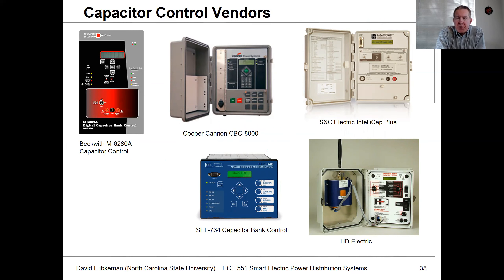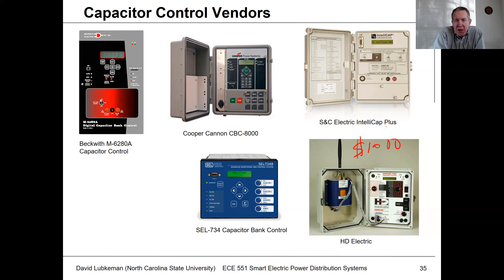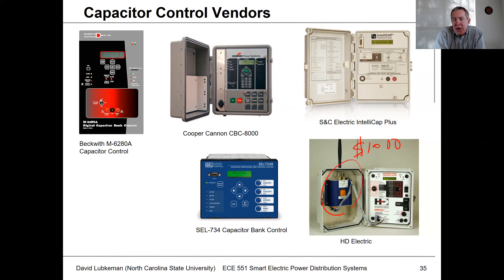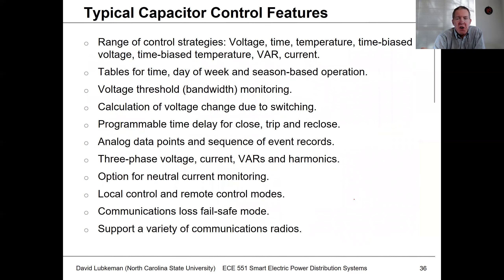This shows what some of these controllers look like. At the low end, these are maybe $1,000 boxes, and with more control functionality they cost more, but they're not really very expensive controls. If all you're doing is controlling on voltage, it doesn't take a lot of logic. Most vendors have a dedicated capacitor control they sell. You can put a radio inside the case and communicate to a device at a remote location. Another slide shows all the different control features available in most common capacitor controls, and you can get the manual for these devices to see what all they can do.